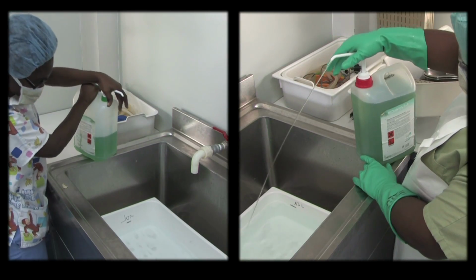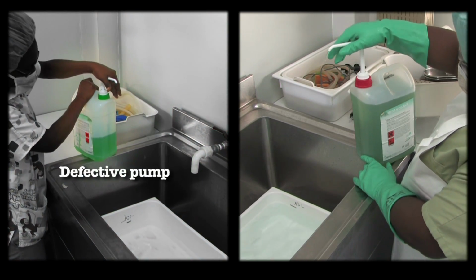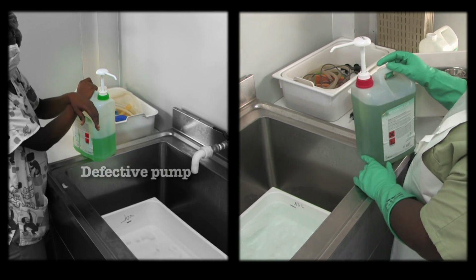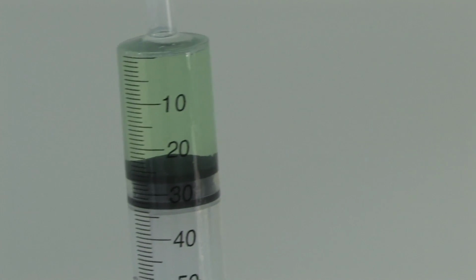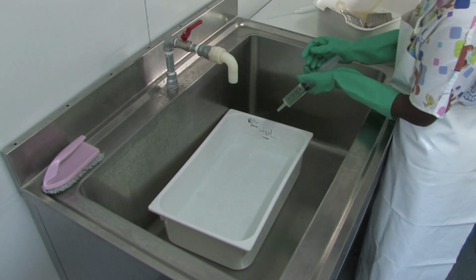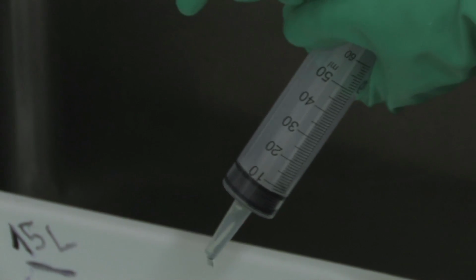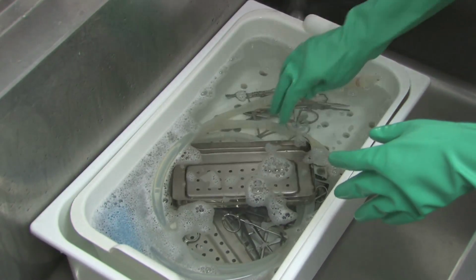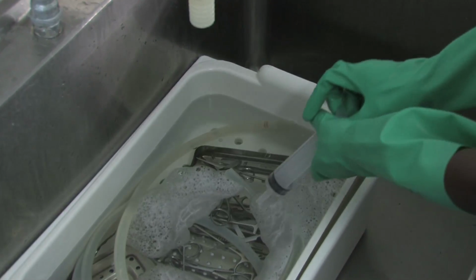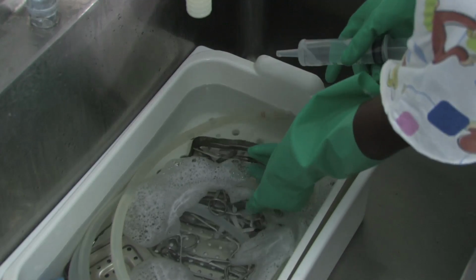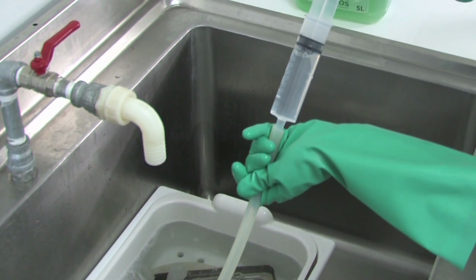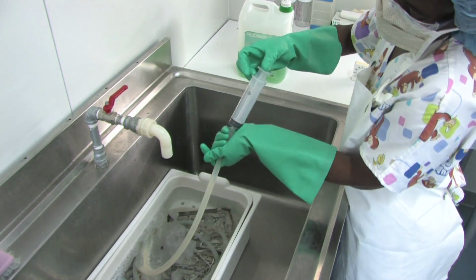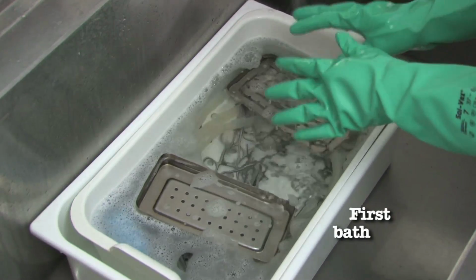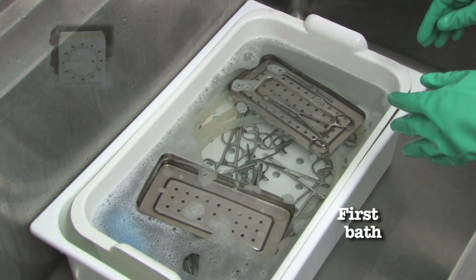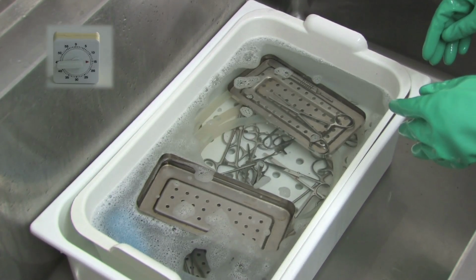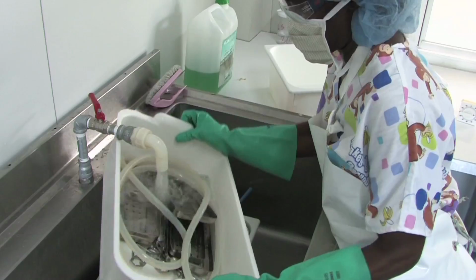Always verify that the pump dispenser is working correctly. If the pump is not working correctly, use a syringe. Draw 25 milliliters for 5 liters of water. Be careful. Make sure that all of the equipment is completely submerged. For hollow parts, such as tubes, use a syringe to ensure that the inside of the tube is in contact with disinfectant solution. Soak for 15 minutes. Use a timer to ensure the correct soaking time. Then empty the bath water into the sink and rinse the instruments under running water.